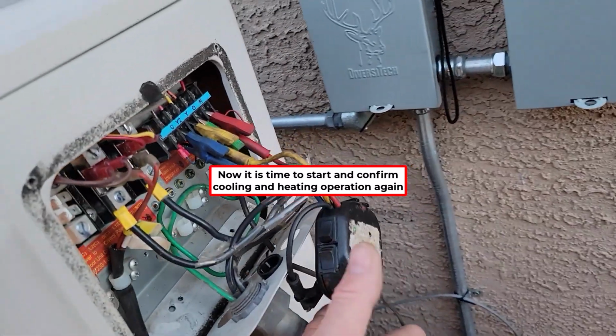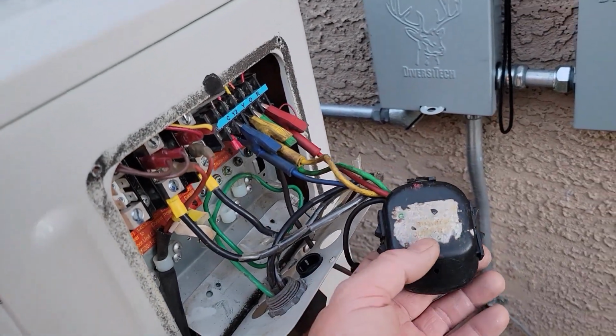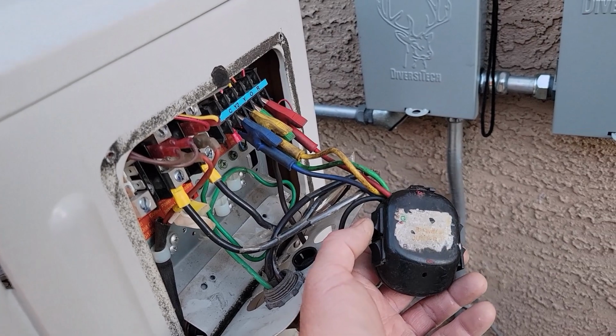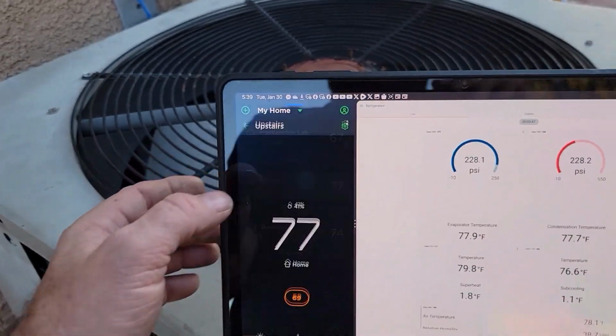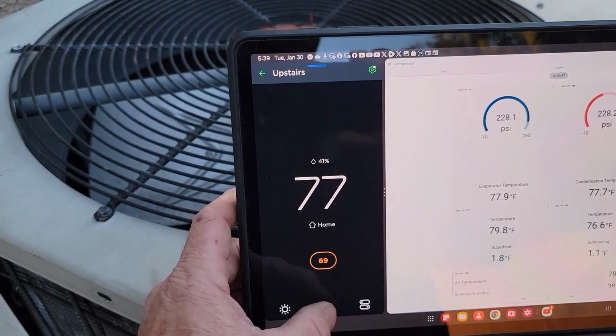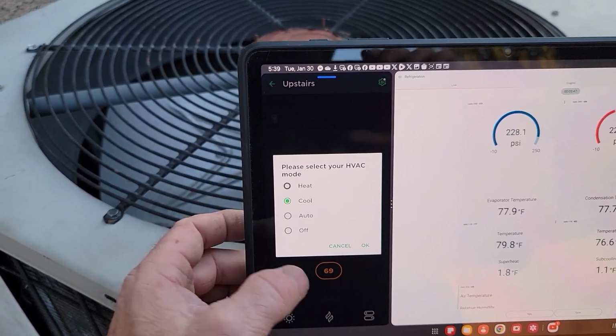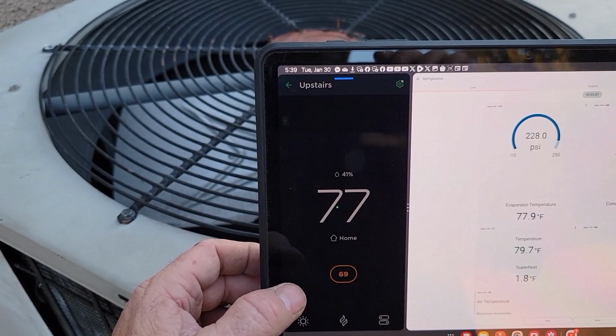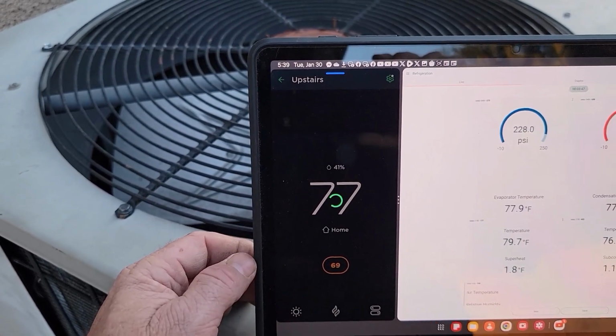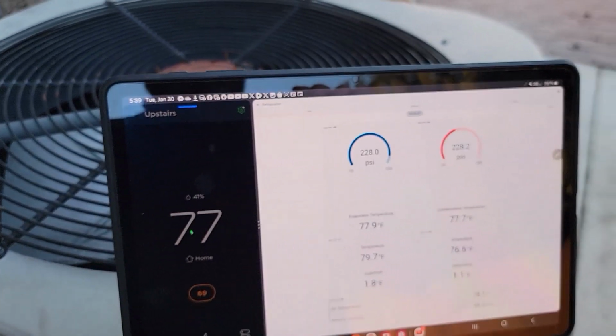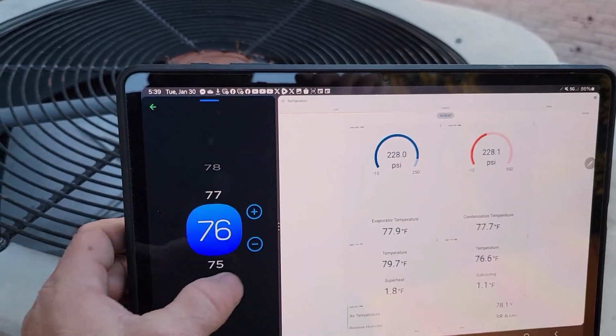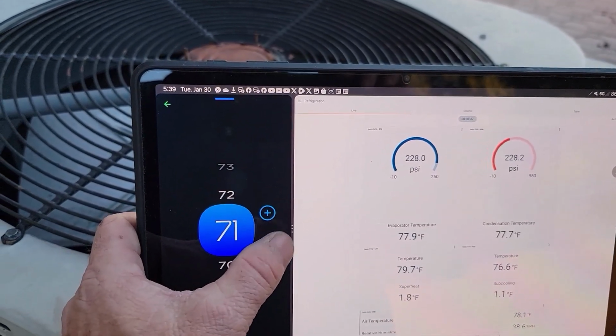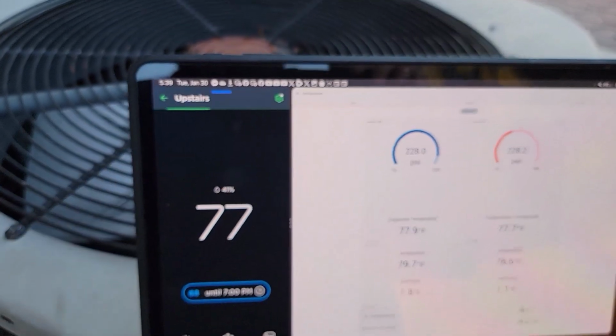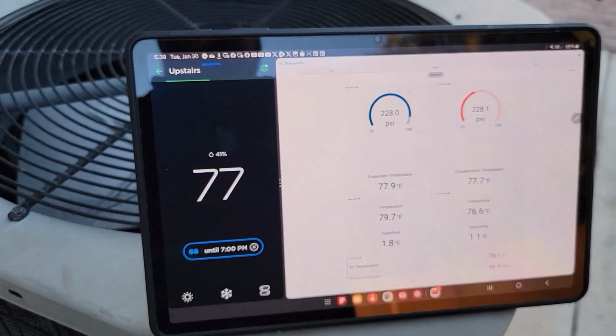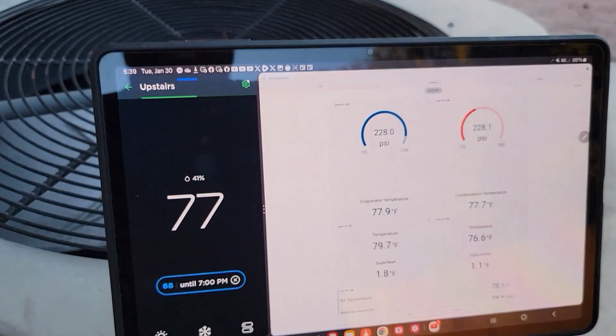Okay, so I have these on, and I did test it just briefly to make sure it started. Turn that back off, so that's all off. We'll just do it by the Ecobee now. So we need to go to cooling to start. It's going to switch modes. And we're going to kick it way down so it goes to second stage, which will run the thing at full 60 hertz instead of 40 hertz. And we'll see what the pressures are like.